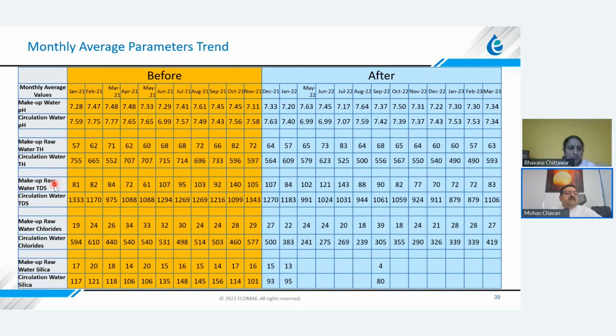If you look at, let's say, TDS, the circulation water TDS, which used to be about 1200 plus on an average, is now about 1000 or below that. And even the total hardness, which used to be about 700 for this particular case, is operating at about 550 on an average, in the 500 to 550 range. So you can see a clear improvement in the water quality by using this technology. Even the silica was in the range of about 120, 140, and it's now about 80, 90 in this range.